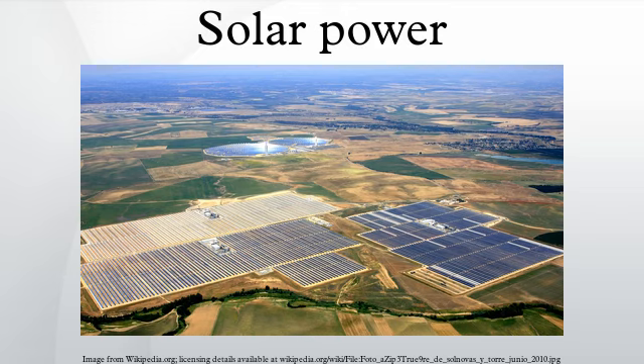Solar energy can be stored at high temperatures using molten salts. Salts are an effective storage medium because they are low cost, have a high specific heat capacity and can deliver heat at temperatures compatible with conventional power systems. The Solar 2 used this method of energy storage, allowing it to store 1.44 TJ in its 68 m3 storage tank, enough to provide full output for close to 39 hours, with an efficiency of about 99%.